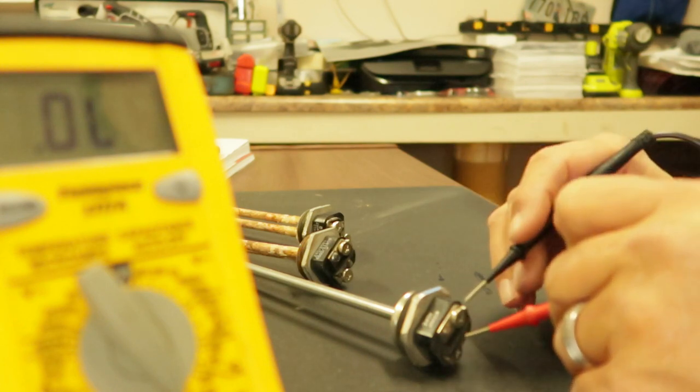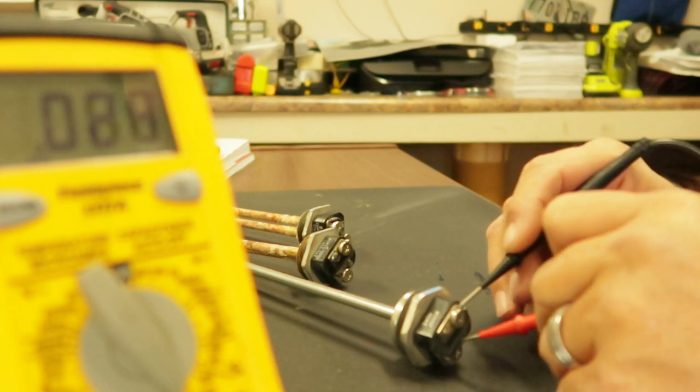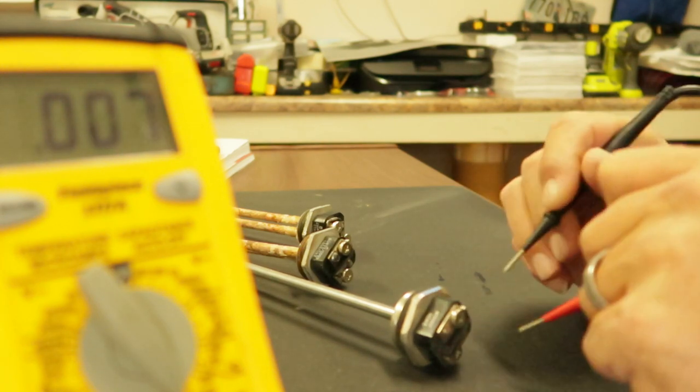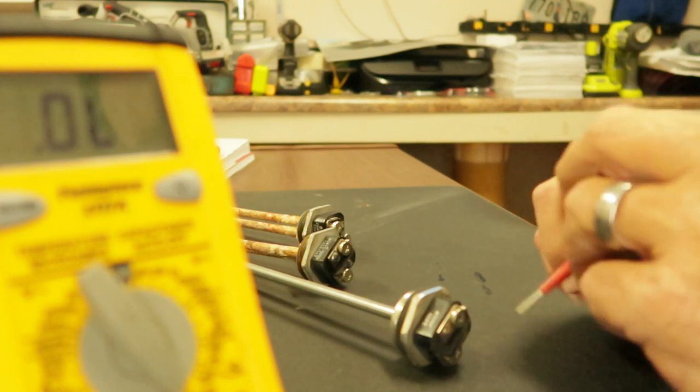It doesn't tell you what your resistance is, but normally if you get a tone on a water heater element, that'll tell you that that element is probably good.